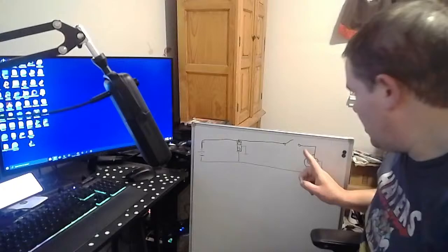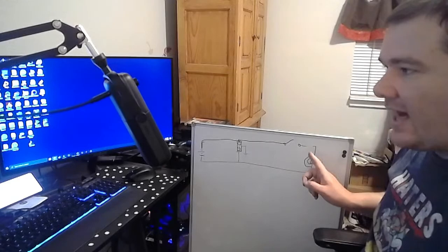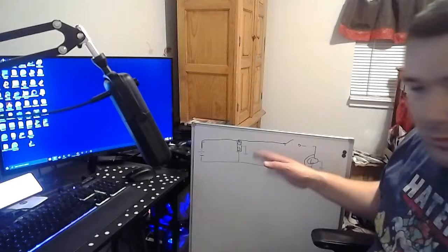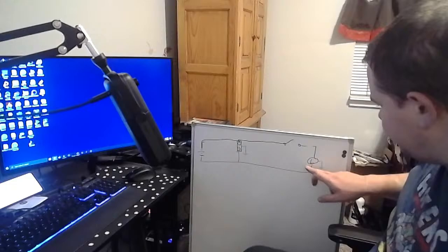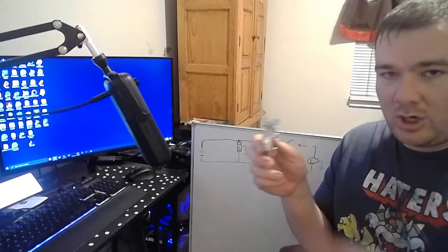This wire right here, this right angle wire, that is your switch leg. This is your feed, your line in, whatever you want to call it. That's how power gets to the switch. That's your switch leg that goes to the device. Let me get rid of our short circuit here. But that's your switch leg right there. And it does not matter which one of these, it could be this way or it could be that way. It doesn't matter because as long as the bridge is down, then current can go across. It doesn't matter which direction the bridge is. Okay.